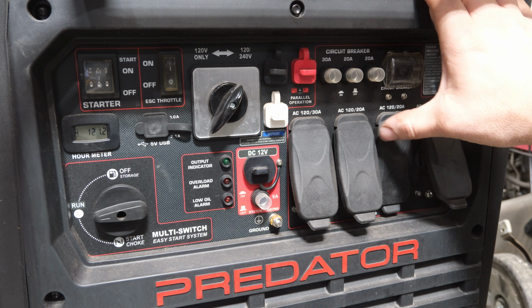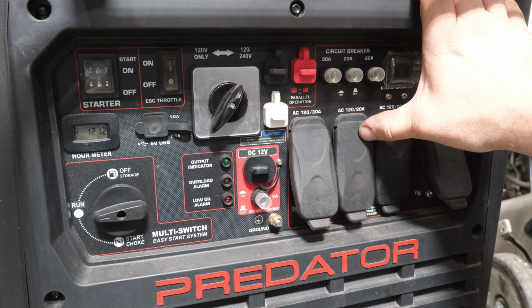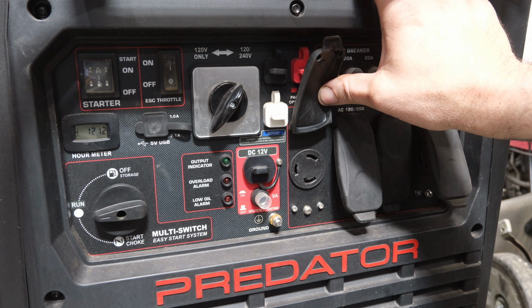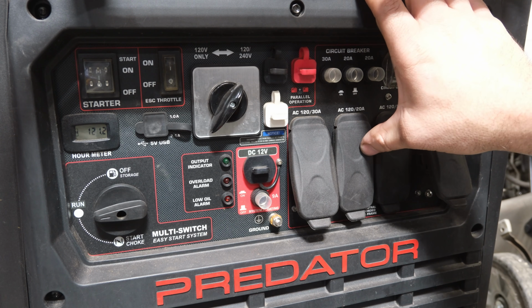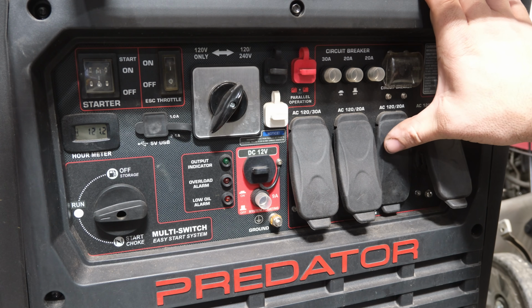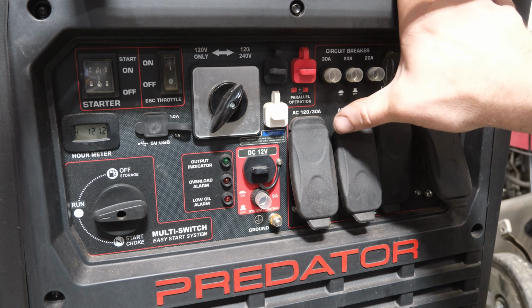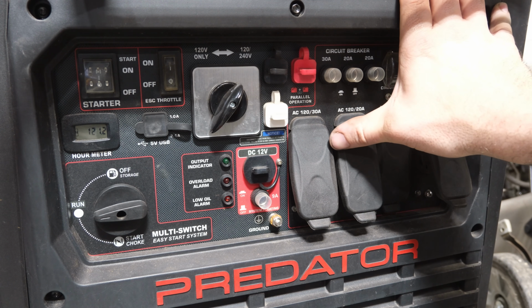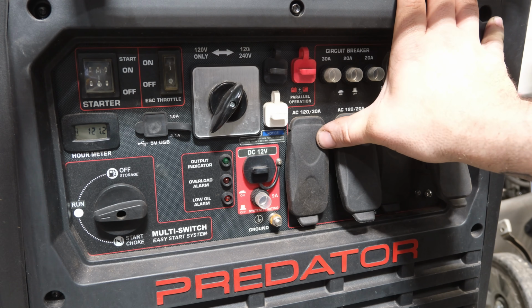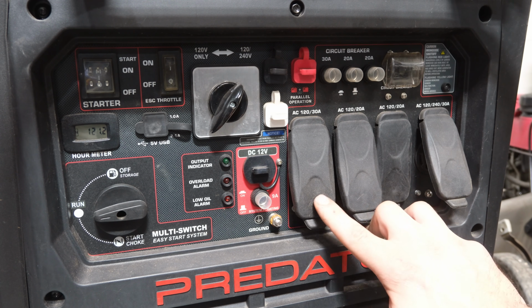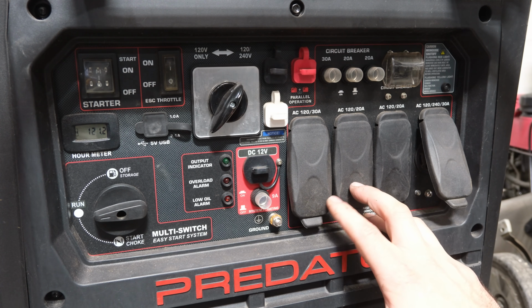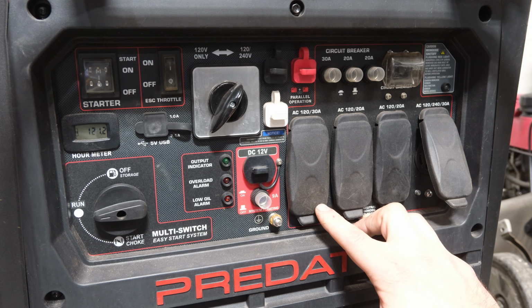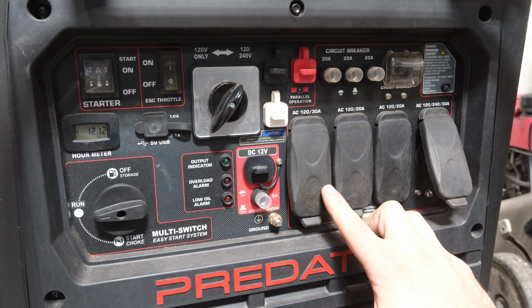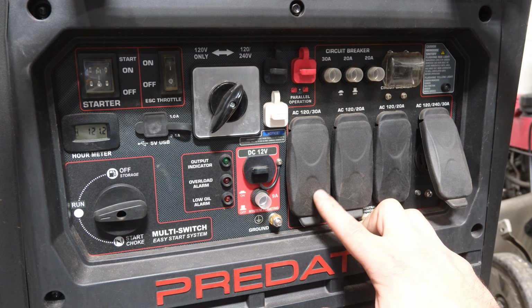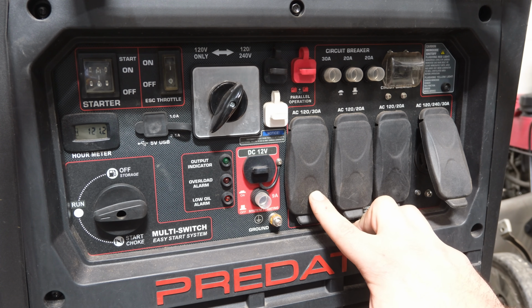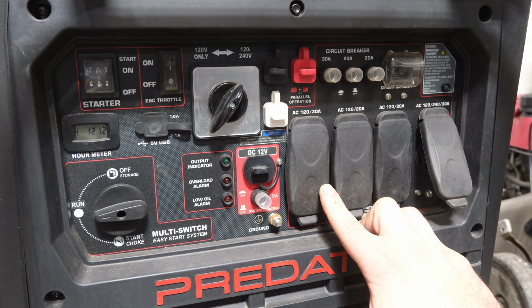Now, you could theoretically run a 20 amp circuit, and rather than running on that, you run on this 30 amp twist lock, and I've tried that with a 120 volt welder. The problem is most 120 volt welders out there actually draw somewhere around 31 to 33 amps in order to output maximum current. Well, that's over this breaker rating, so this is going to trip. So that is a severe limitation you're going to run into, and that is why anytime someone asks me about running a 120 volt welder on a generator, the feasibility of it, I universally say good luck, because almost all of them are going to simply overload it, trip the breaker, and cause problems.